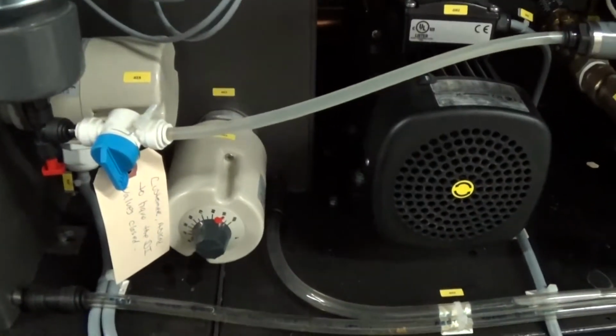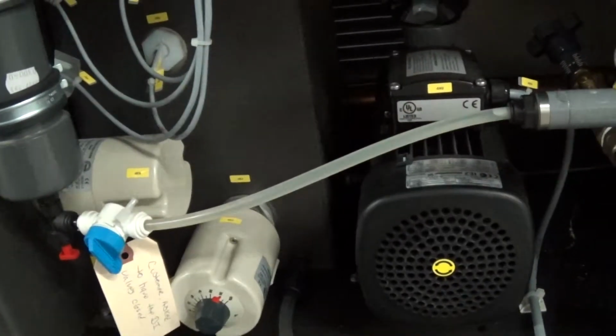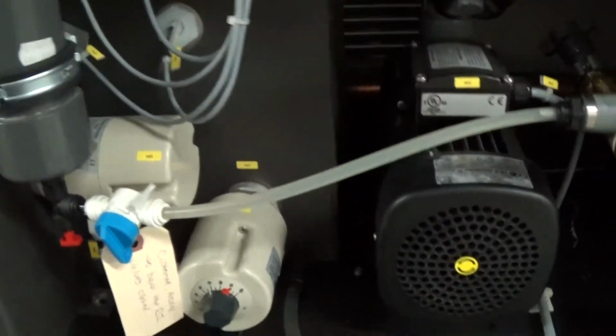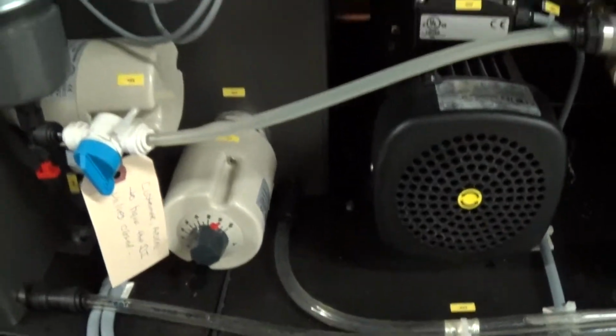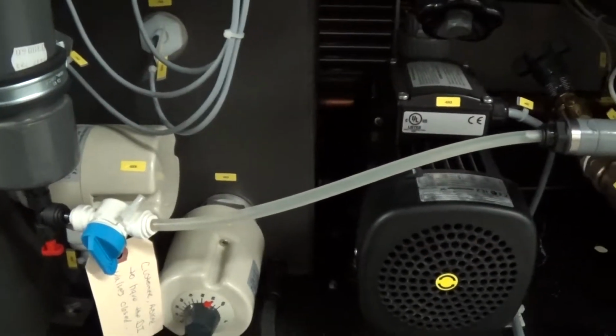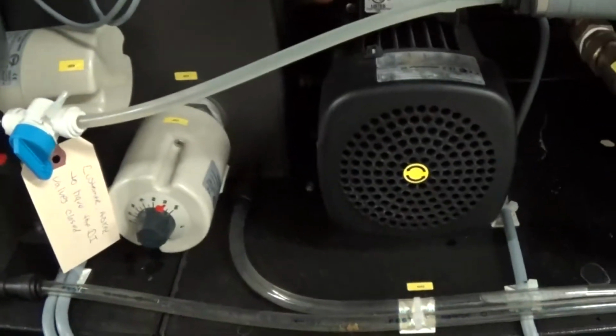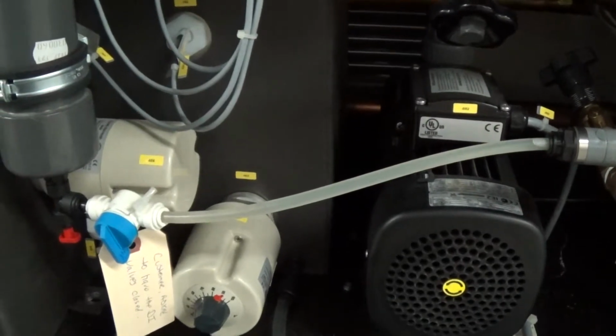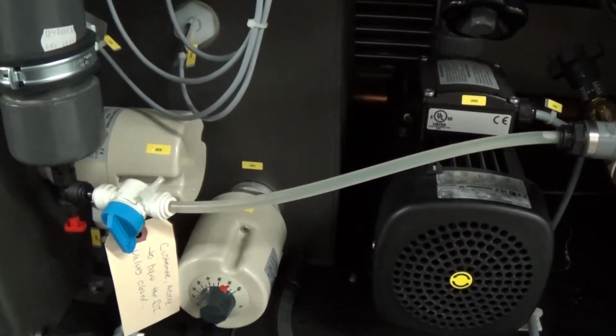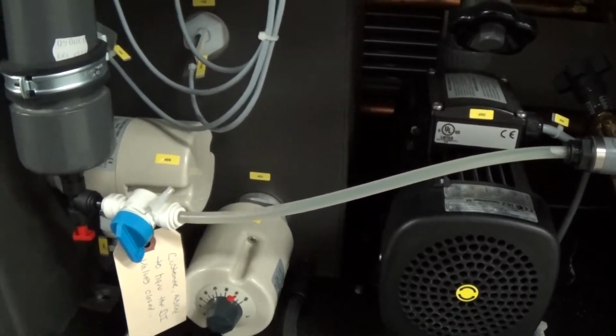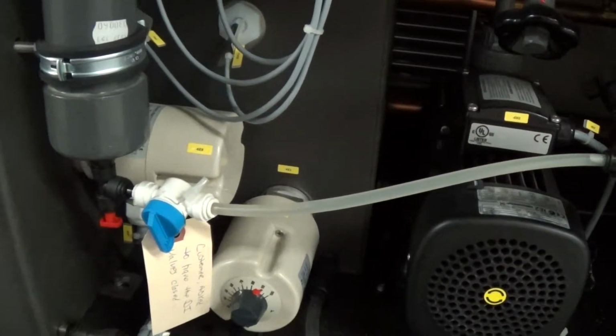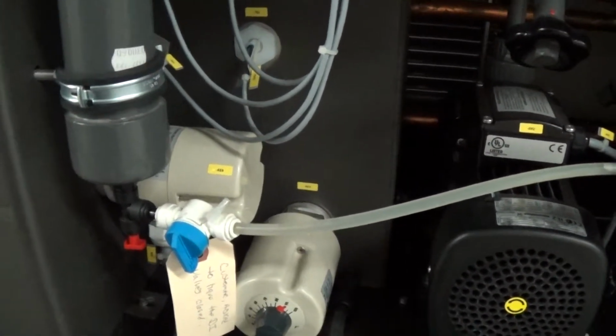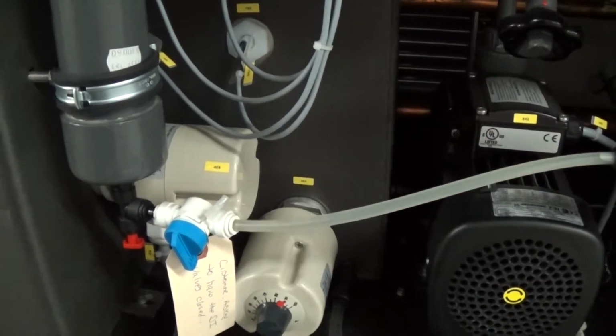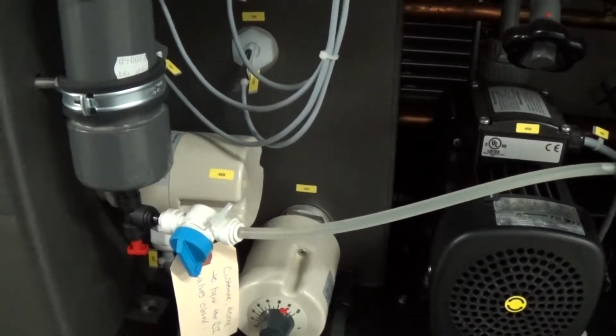In both cases, the unit has these little heaters for each one of the tanks, which is also something that you don't need to use. But for us here, for our testing, it was kind of convenient because we could turn these heaters on to give a little bit of load during our testing. But for both these, the temperatures inside the controller that control these heaters will be turned so low that they're not going to turn on. It's not going to be relevant for your application.